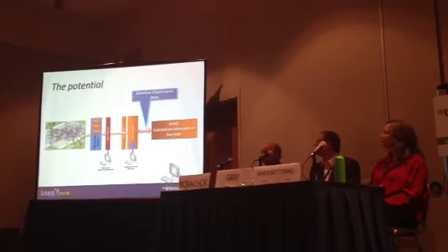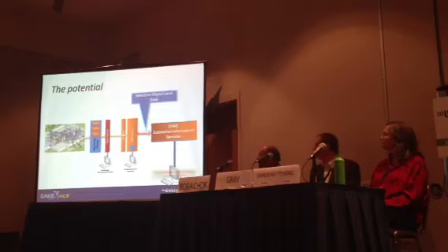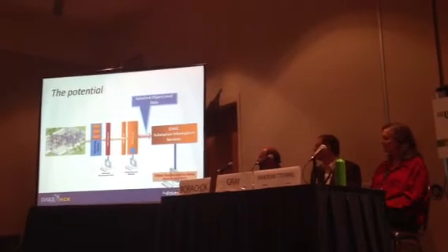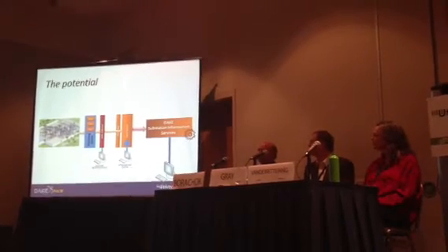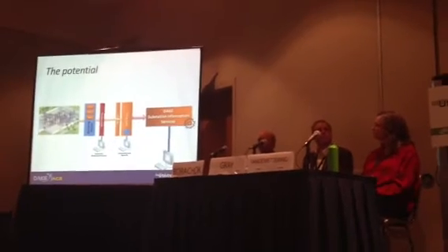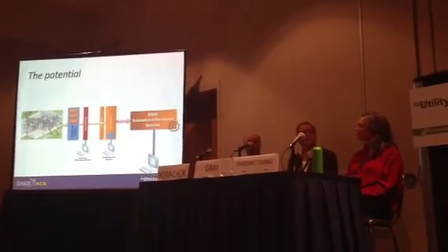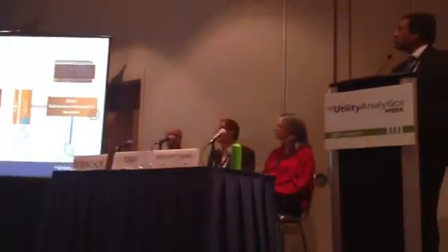And then there's a rules engine that can configure your rules. We call it object communication setup. You configure them, and then you can execute. The rules are now run on the event data on the fly, in real time, and produce, on a line diagram at a substation level, alerts passed onto the picture. So we haven't used SCADA or anything. We've connected directly to the monitoring devices, pulled in the data, taken it into the data server, and through the services layer exposed it.